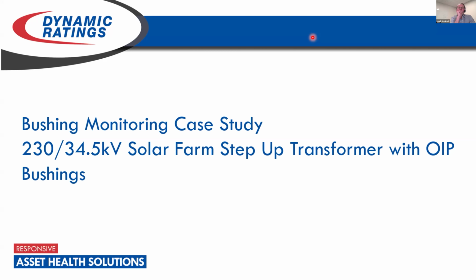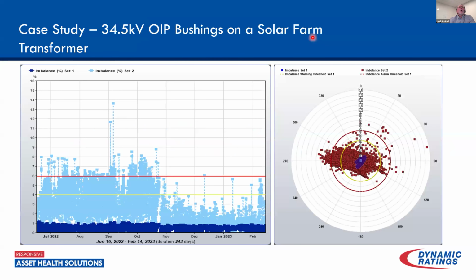As you're doing that, you could also create some voids in the insulation, resulting in partial discharges. But we also have the harmonics, and what the harmonic impact is going to be on those dry type bushings as well is something we need to be concerned about. But in this case, it was oil impregnated paper bushings. Here I've got both high side and low side monitoring.